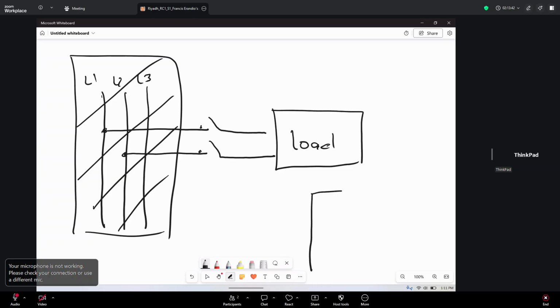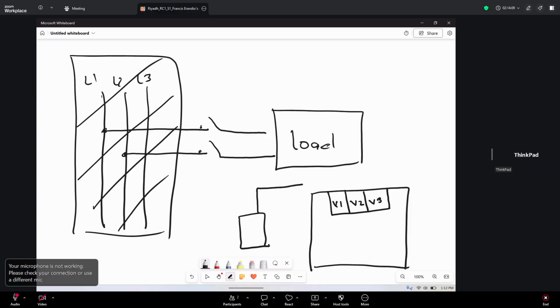At the terminal of the meter, there is a terminal for voltage inputs. What you are going to do is connect one of your tester leads to V1 of the meter, and then test the other lead on each line, first this line and then the second line. Whichever shows 0 volts means that is line 1. For example, if it becomes 0 volts here, then you can identify the first line to be line 1.